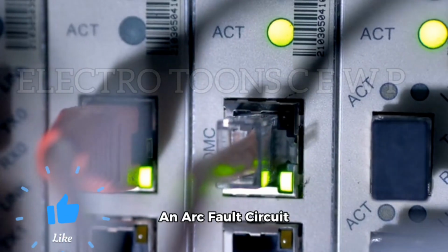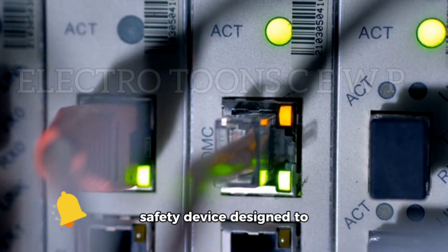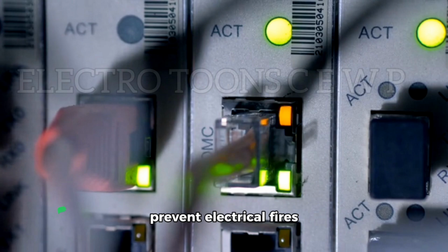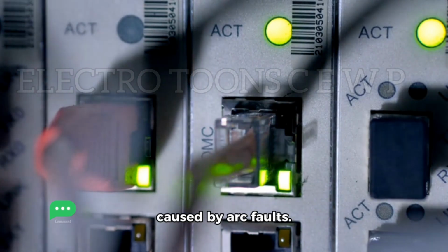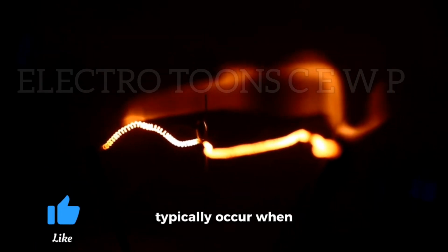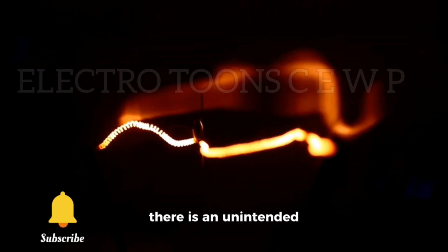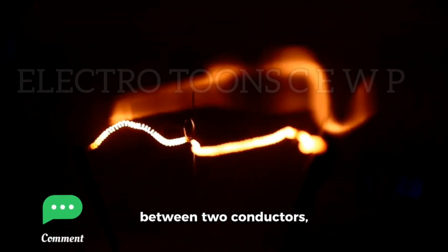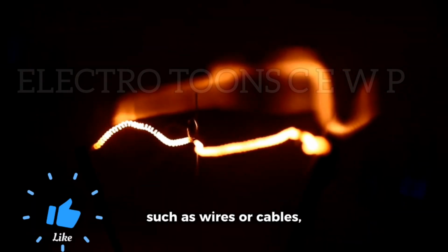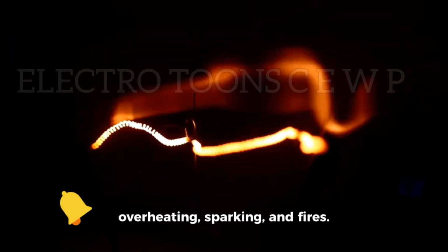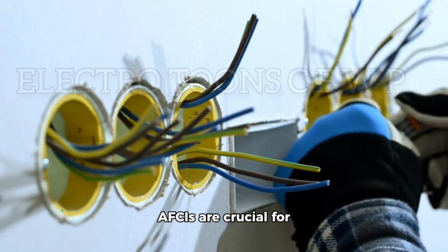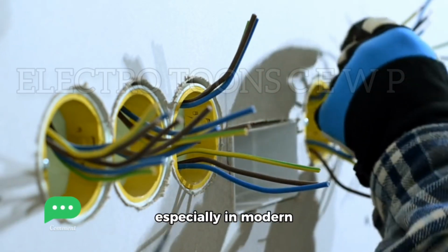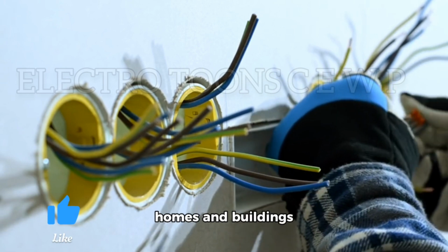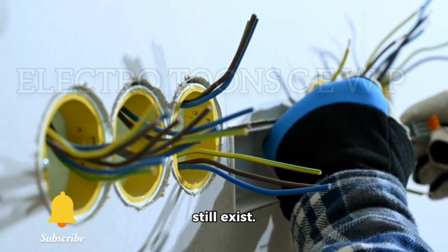An arc fault circuit interrupter, AFCI, is a safety device designed to prevent electrical fires caused by arc faults. These arc faults typically occur when there is an unintended electrical discharge between two conductors, such as wires or cables, that can lead to overheating, sparking, and fires. AFCIs are crucial for electrical safety, especially in modern homes and buildings where older wiring may still exist.